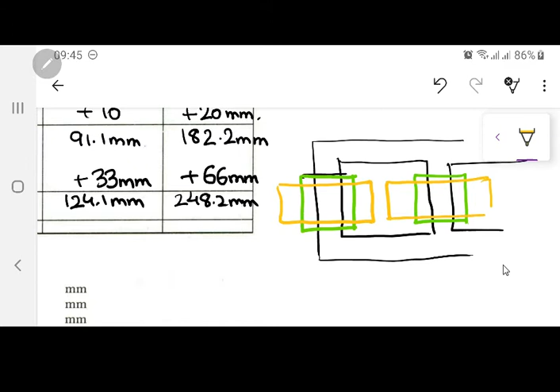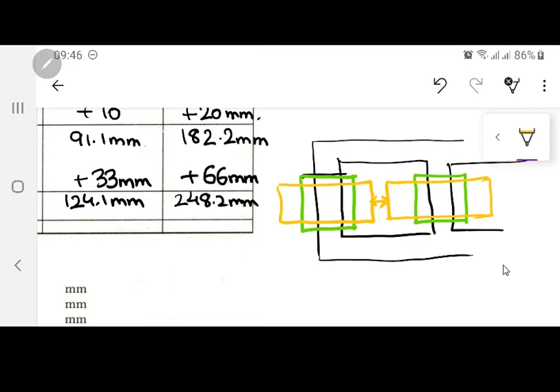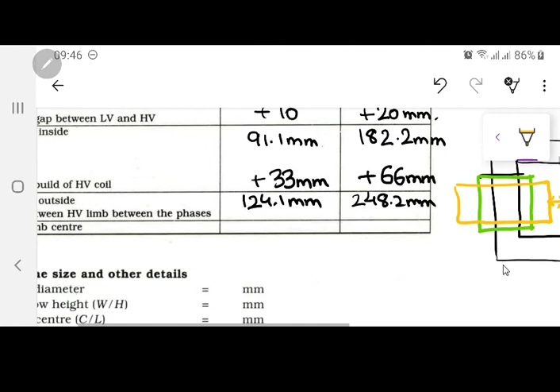Now this distance is also very important and critical. Why? Because there is going to be a voltage difference between them. If it's an 11 kV transformer, they are A phase and B phase, so there is certainly going to be an 11 kV voltage difference or potential drop between these two. So the gap kept between the high voltage limbs between the phases - according to this book, they have kept this gap at 13 mm.